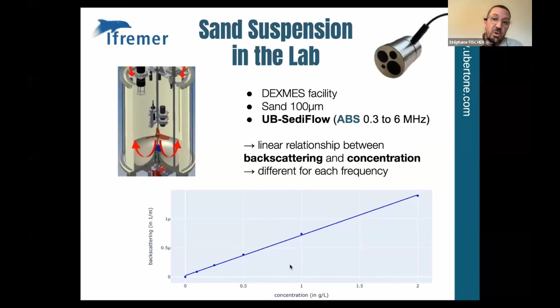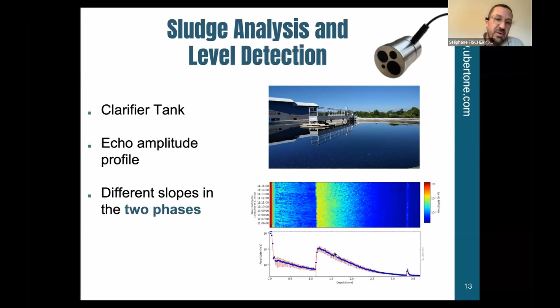Here's another example of backscattered echo in a wastewater treatment plant. Here we are in a clarifier tank with a sludge level at about 1 meter depth. The system is looking down, and what we detect easily is the first step, which is the sludge level, and then we have attenuation from the sludge itself. The interesting point here is that the attenuation in the water with suspended sediment and the attenuation in the sludge are quite different, and this is due to the density of the materials.